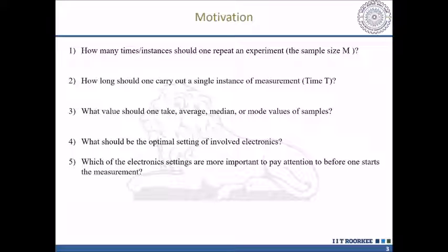We have ordered sodium iodide thallium scintillator detectors in our lab, which is Divyadrishti Imaging Lab, located at the Physics Department, IIT Roorkee. My supervisor asked me to set up those detectors. I was aware of some methods which are frequently used to calibrate the detectors. When I started to use those methods, I realized that they were dealing only with the calibration of voltage. Then what about the other parameters like amplifier, lower and upper limit of discrimination, and energy window?